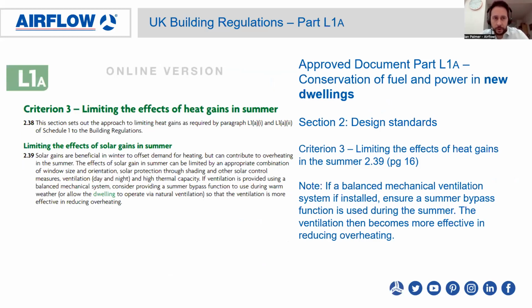In Section 2 in L1A, inside Part L, it covers design standards and criterion 3, limiting the effects of heat gains in the summer. So there's a note here: if a balanced mechanical ventilation system is installed, ensure a summer bypass function is used during the summer, and the ventilation then becomes more effective in reducing overheating.